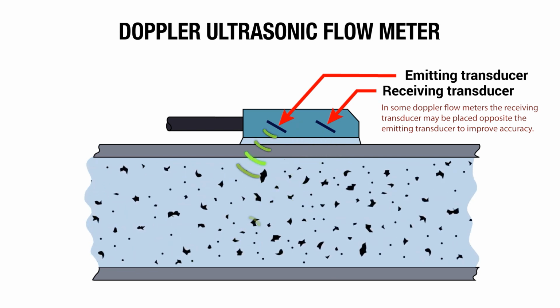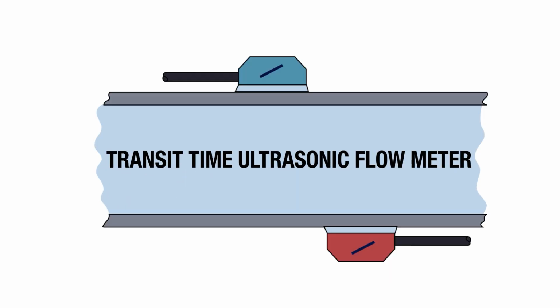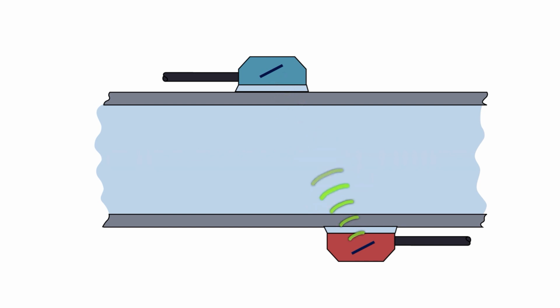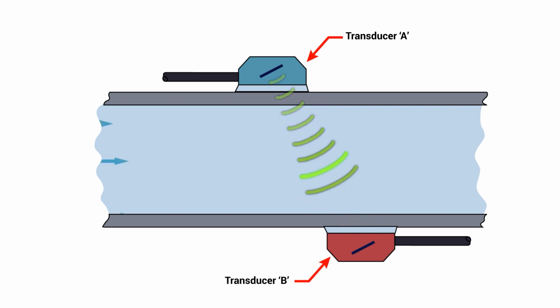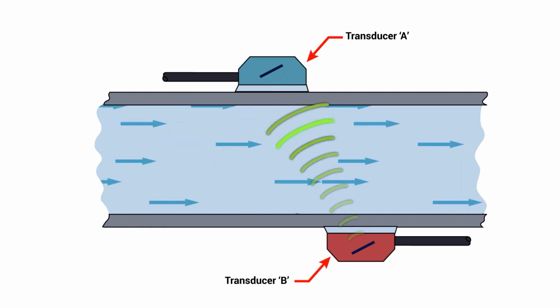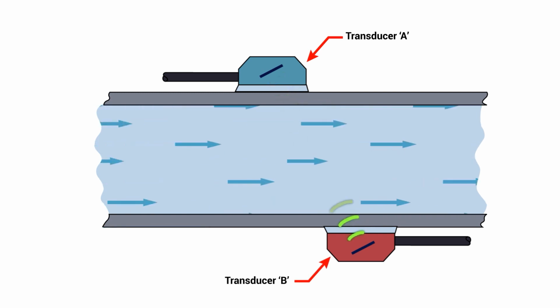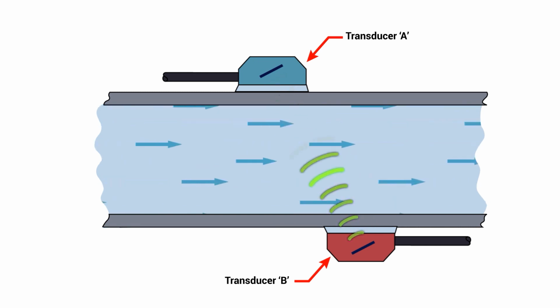On the other hand, the transit time principle calculates the flow rate from a shift in the transit time of the ultrasonic waves. In contrast to the Doppler, the transit time ultrasonic flow meter is best used for clean liquids such as water or oil.